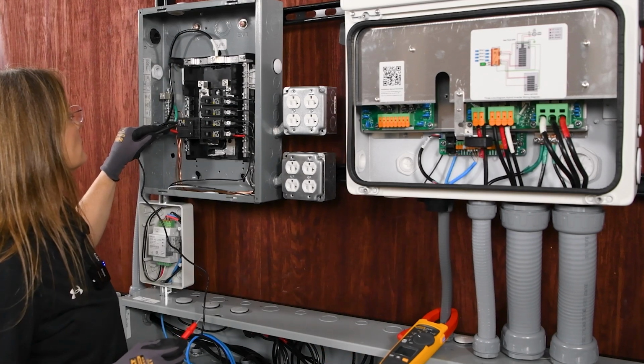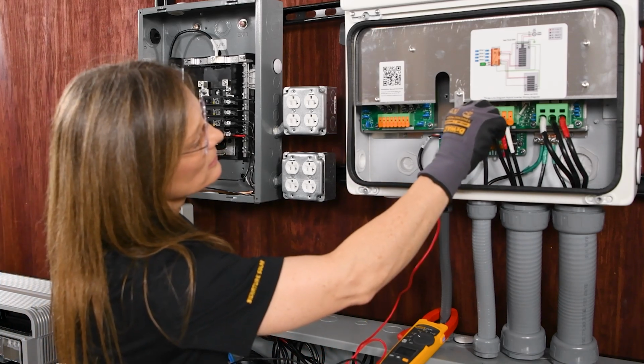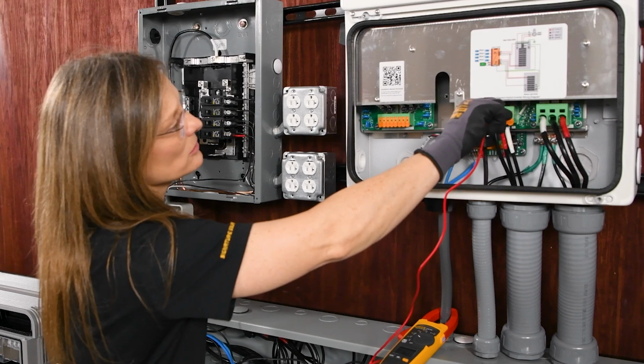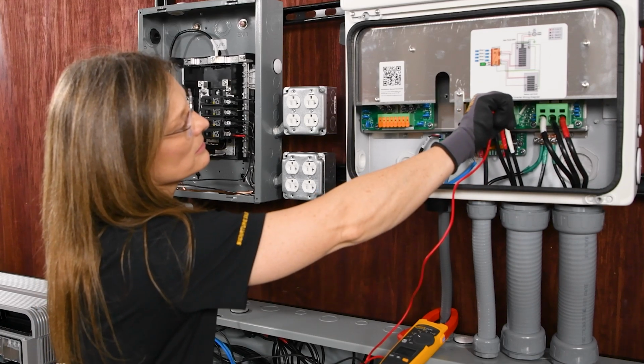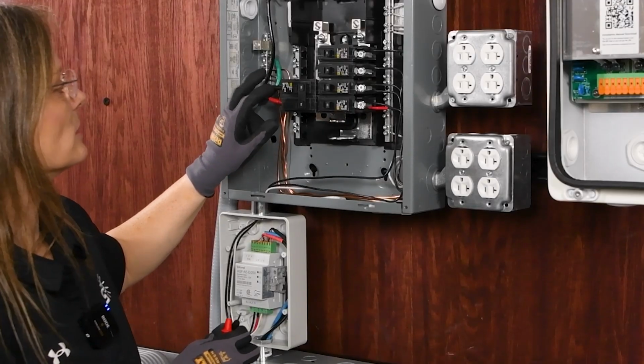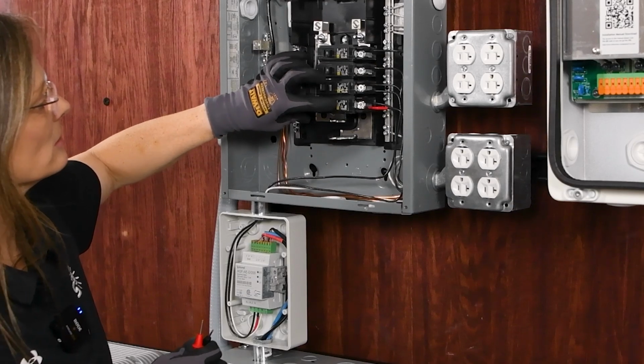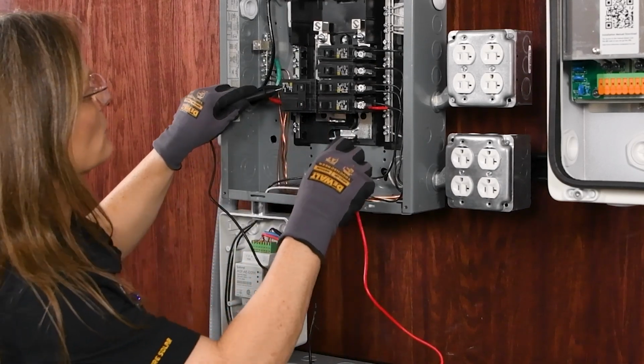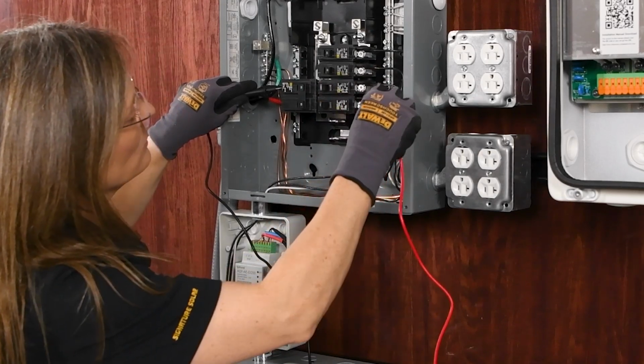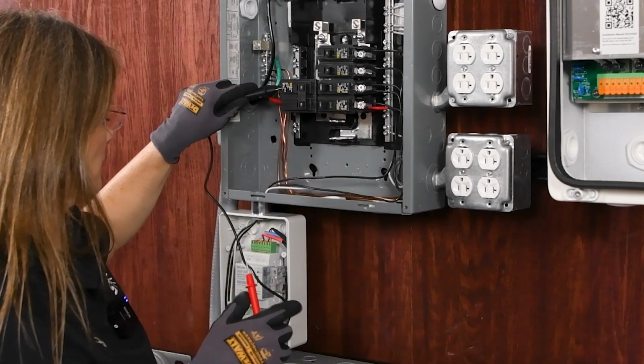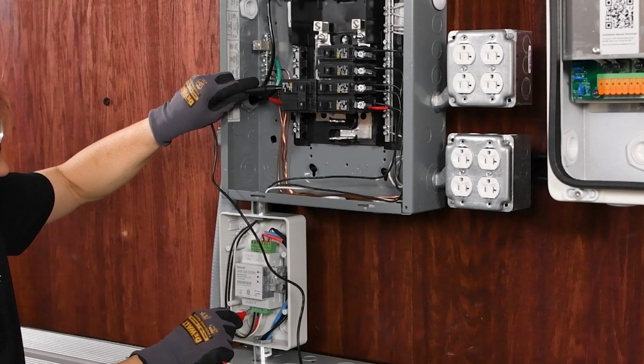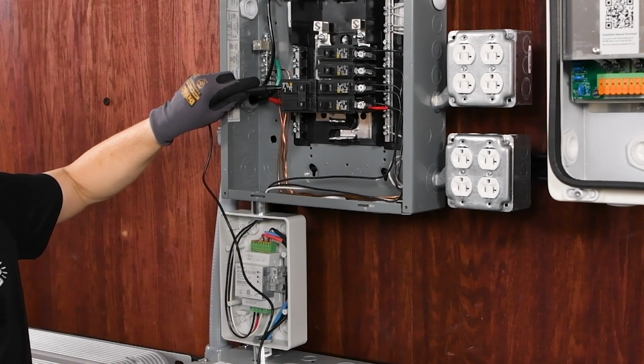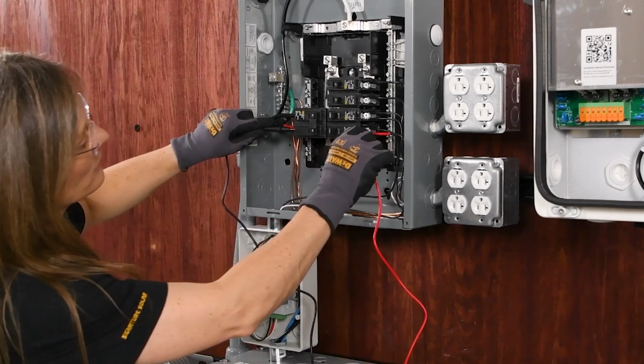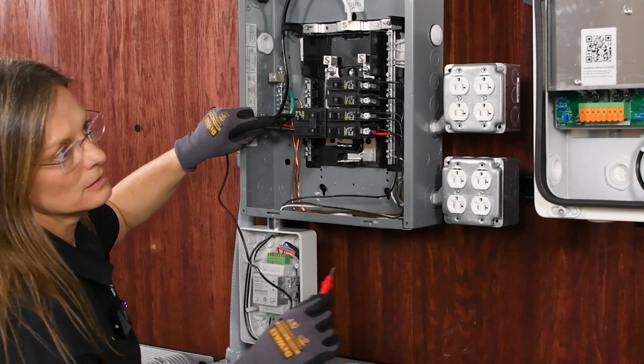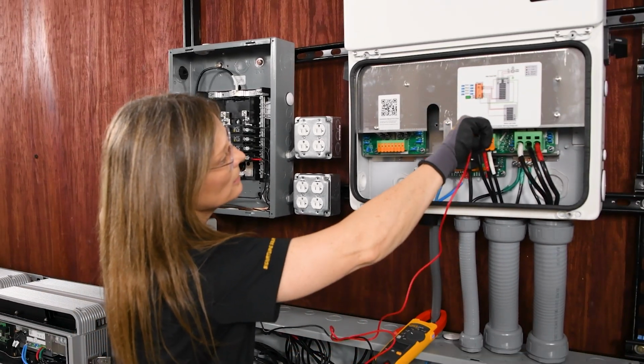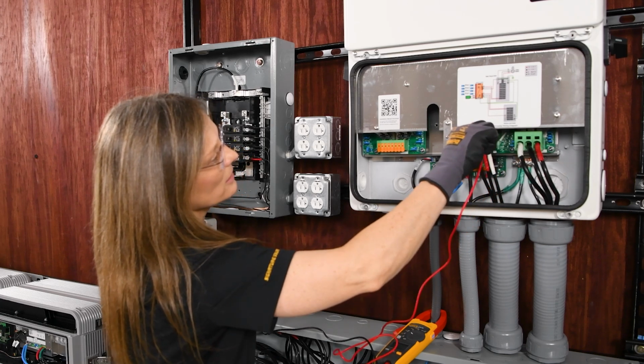We'll also check the continuity from our backup panel here to the backup panel of the inverter. Okay, we have good continuity from L1, and we make sure that it is not crossing phases with the other two, so we're good there. Now to make sure that we haven't crossed phases on our meter, we'll have to flip the breakers that our meter is connected to, make sure that they are both on, and we'll go L1 to the L1 connection. We have continuity there, and we make sure that we don't hear anything on the others. So they are on the same phase for L1, and then we can also check it where L1 is connected here by touching the screw there and making sure that it's not getting any continuity across the other two. We can do the same thing with L2, check all of the red, and then make sure that nothing else is giving us sound.